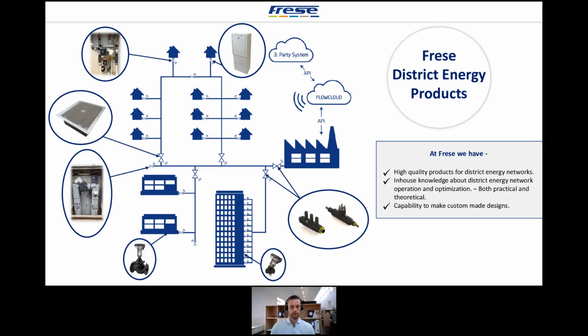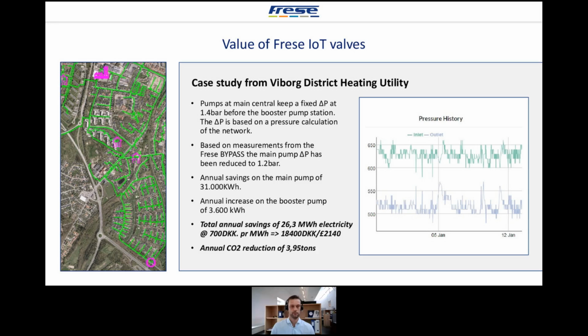Yes, I'll take a closer look at a case study we made where we actually started to use some data, and this is the pressure data that we were very interested in. In this case, we had a district energy operator. They started to install some of our products out there. It was end-of-line bypasses to get more knowledge about the pressure throughout their energy network. What they found out was that they have been running their system based on a calculation, and the set point was set due to that calculation.